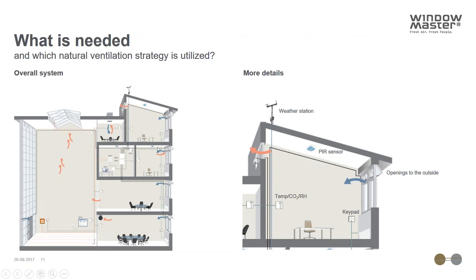Natural ventilation is controlled based on indoor air temperature, CO2 level, relative humidity, outdoor air temperature, wind speed, wind direction, and rain. It is controlled using actuators linked to a dedicated control system — what we call NV Comfort — or a BMS system. We offer a complete solution from design, to supplying components, to providing the control systems for these kinds of buildings.